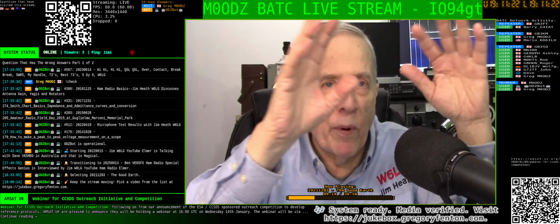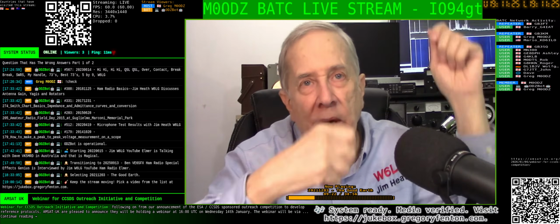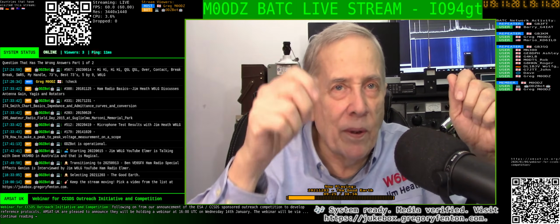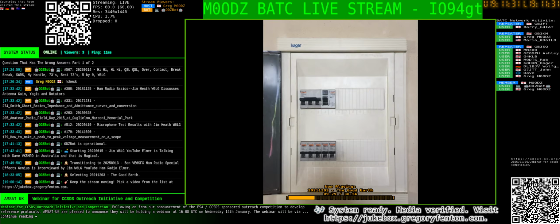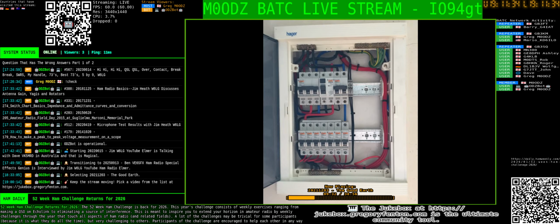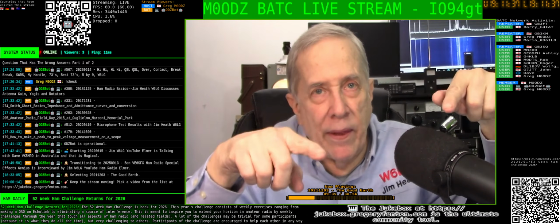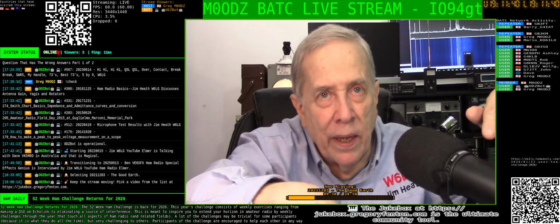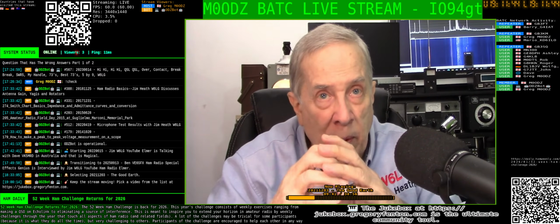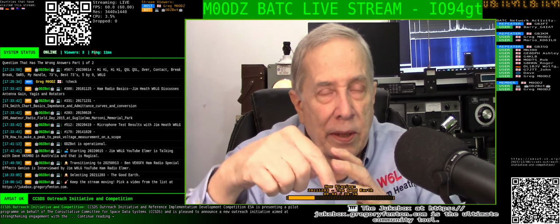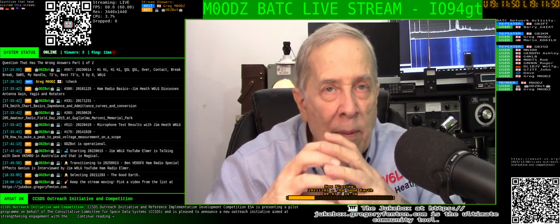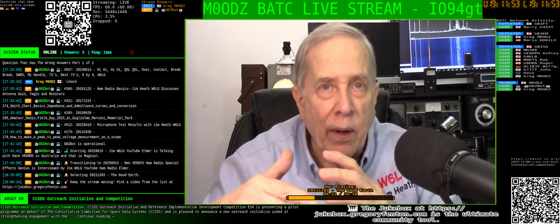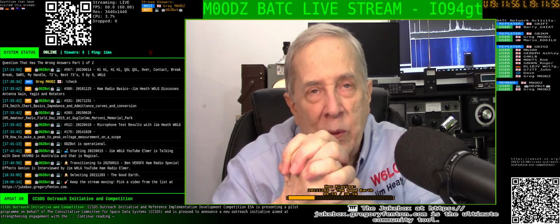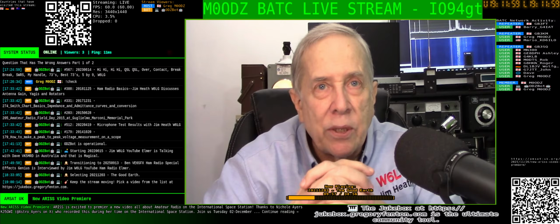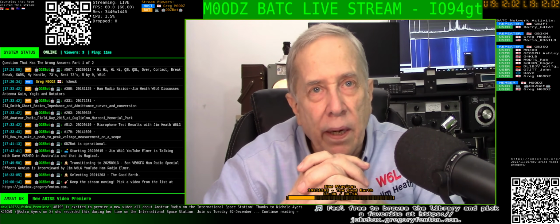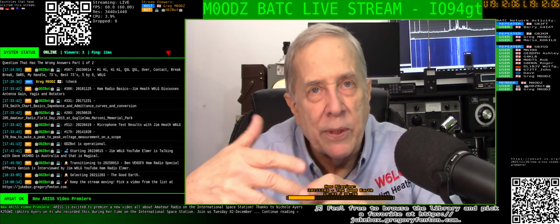So what you're saying is if we opened the cover and removed the interior cover on the console or the main panel, we would find a ground bar and a neutral bar, and they're tied together at that point. Yes. And those two tied together go down to a common point box, and then from that box it goes to the ground rod. And in that common point box, the TV, gas line, and water lines all come together as one ground. Also, as far as leakage goes, those devices still aren't in common use here, where it would trip at 45 milliamps or so.